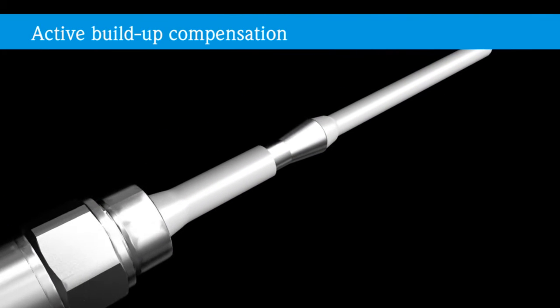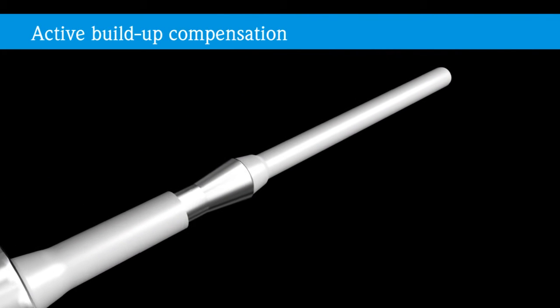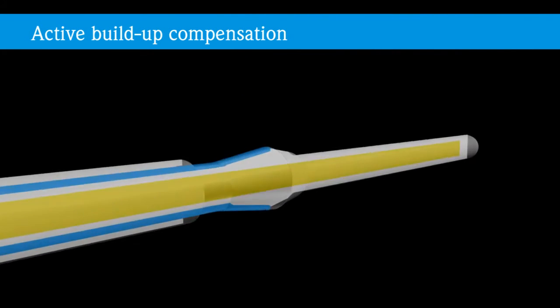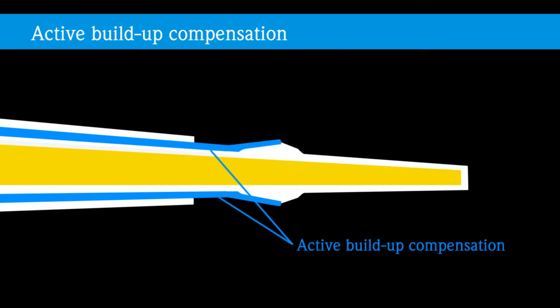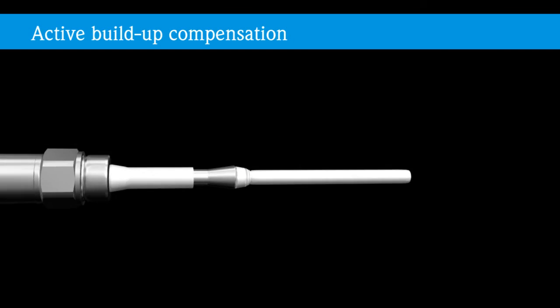Endress+Hauser has developed a capacitive probe with active build-up compensation. The probe has an additional protective electrode with the same potential as the measuring probe, which not only generates one electric field, but two identical fields.